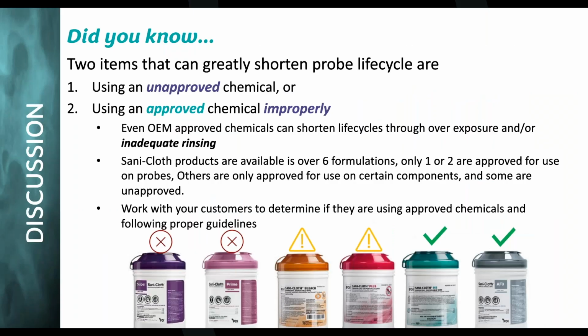And the two items that can greatly shorten probe life is chemicals. So either people use an unapproved chemical. We saw this a lot during COVID. I had one customer who called me and said, I keep going through lenses on your probes. What are you guys using? Whatever you're using, it's not working. I'm like, well, we use an approved material. It's the same as the OEMs. And I went and visited them, and they were soaking their probes in chlorine bleach because everybody was so paranoid about over sterilizing. Well, it's a good disinfectant. It will kill all bugs, but it also kills probes because you can't use chlorine bleach on any probe.